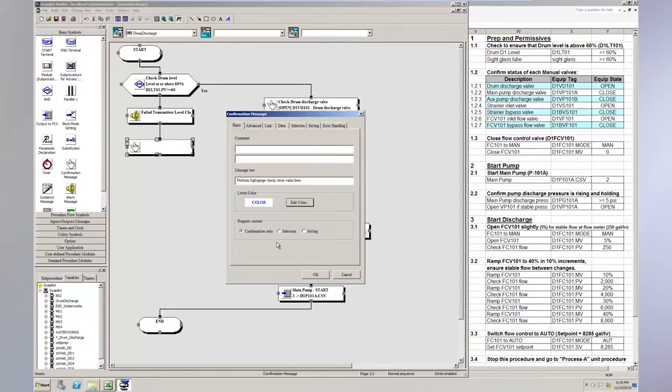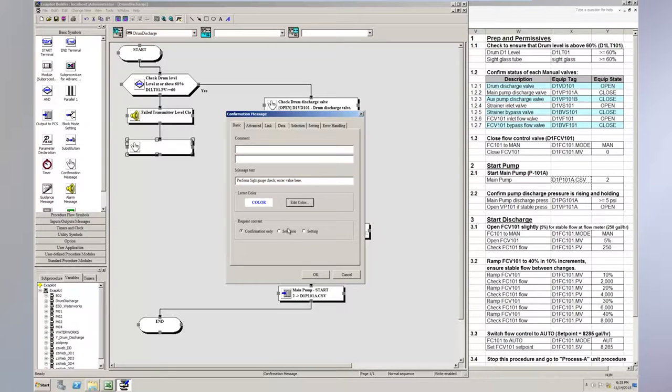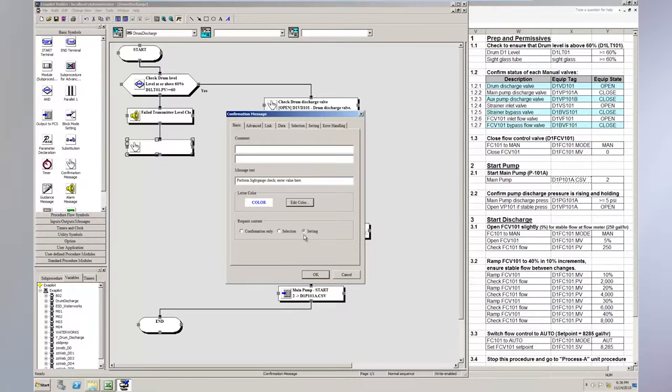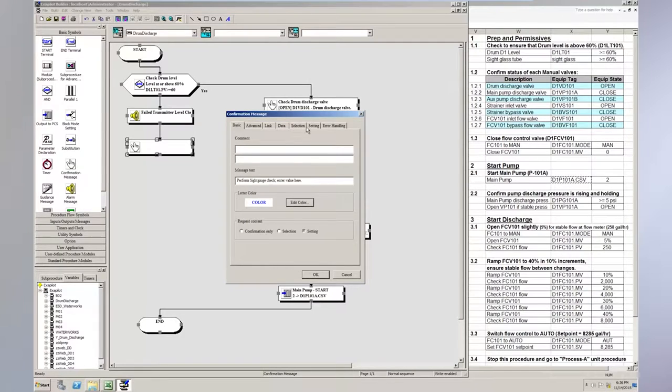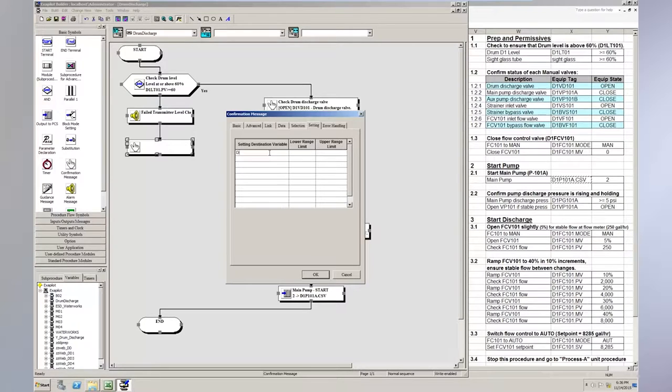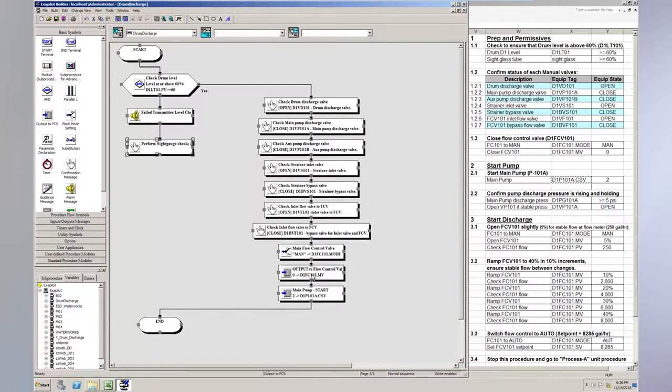And since this is an operator action, I'm going to make this blue. And I'm going to show you a feature of the confirmation message that I talked about earlier, but I didn't demonstrate it. So you have three choices on a confirmation message. You can have confirmation only, selection, and setting. So under selection, this selection is what you'd use to then configure a set of selection buttons for the operator to select. In this case, I'm not going to do that. I want the operator to actually enter a value. I want to read the site gauge and enter a value. So I'm going to select setting. And then we can go to the setting tab here. And I can enter in a value. I'm going to call this drum level. And it'll be zero to a hundred. I can bound this to be zero to a hundred percent.